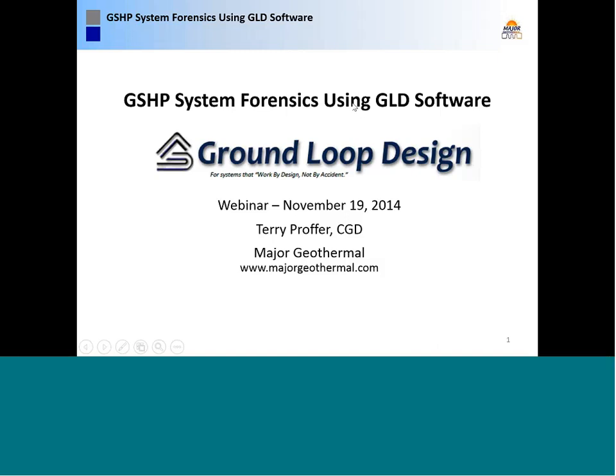Well, welcome all. What we're going to do is go through some examples for some forensics efforts, and what I've done is selected 3 projects where we've used GLD to assist in the evaluation of why we had problematic systems. And anyways, it's a pretty good tool because you can use GLD to reverse engineer a ground loop if you have all of the preliminary design inputs, or if you have to remanufacture them yourselves. So that will get started.